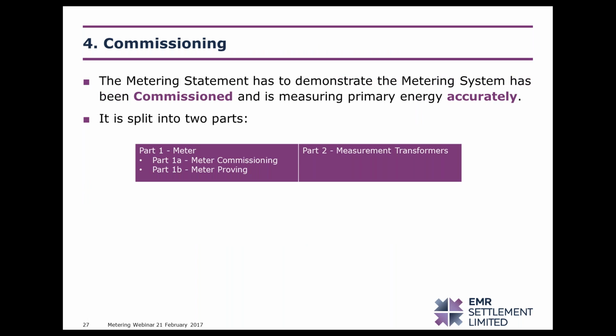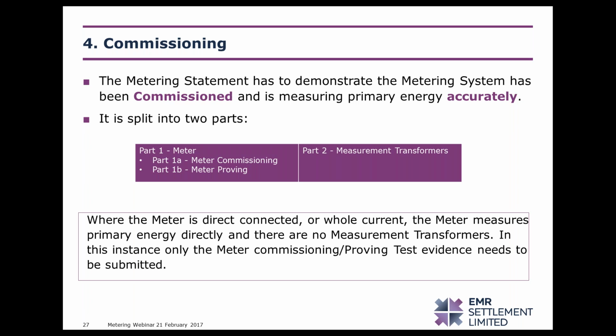The next problem area has been commissioning. The purpose of commissioning is to demonstrate that the metering system has been checked, to prove that it has been installed and configured correctly, and it is measuring primary energy accurately. It can be considered in two parts. Firstly, the meter, which is subdivided into the meter commissioning tests and the meter proving tests, and secondly, commissioning of the measurement transformers.